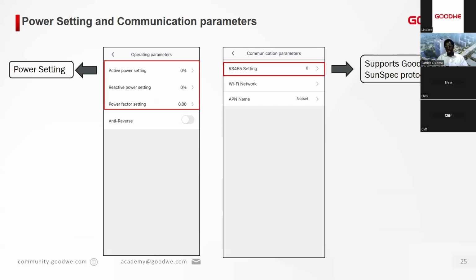In case you're putting in a controller, you can also do the RS485 setting. It supports the GoodWe and also the open source SunSpec protocol. Therefore, what we'll be doing here is setting the Modbus address of each inverter so that they are seen as different.